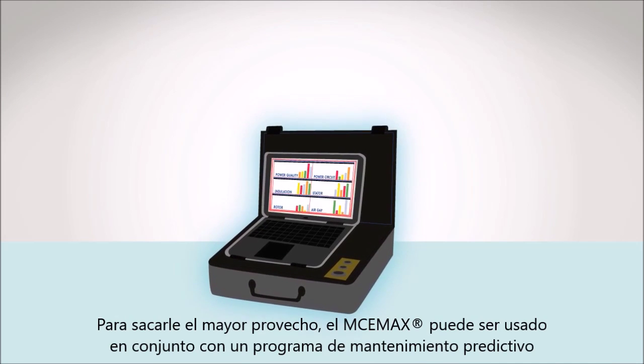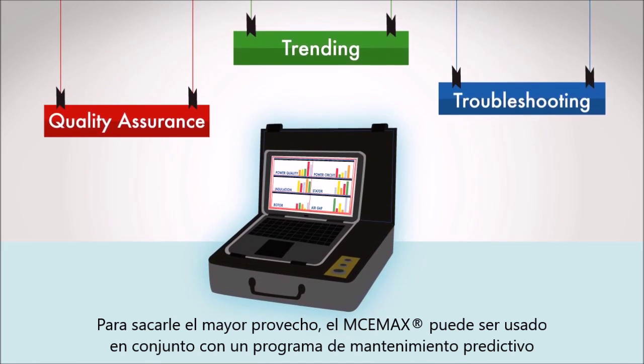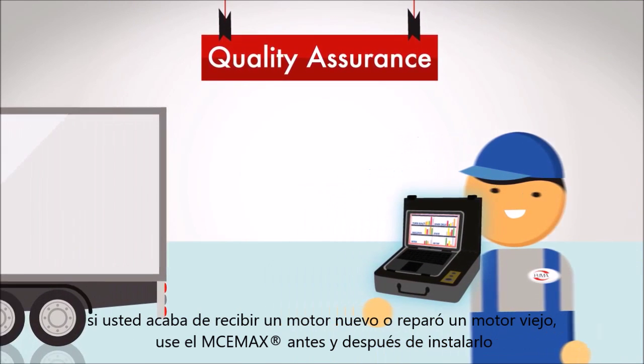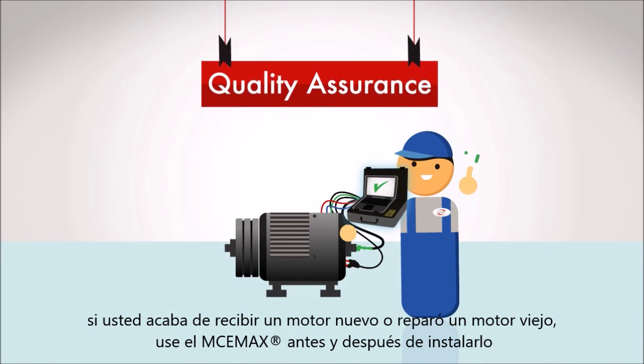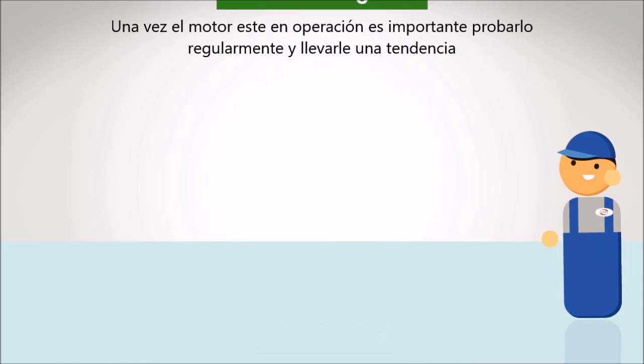But in order to make the most of it, the MCEMAX should be used in conjunction with a complete predictive maintenance program. And any good program begins with quality assurance. Whether you've just received a new motor or had an old motor repaired, use the MCEMAX before and after installation to make sure the motor's working properly from the beginning.